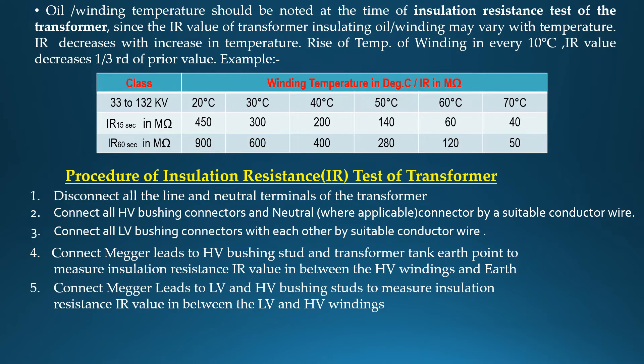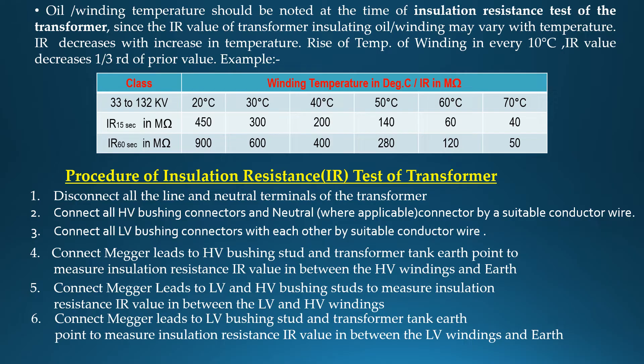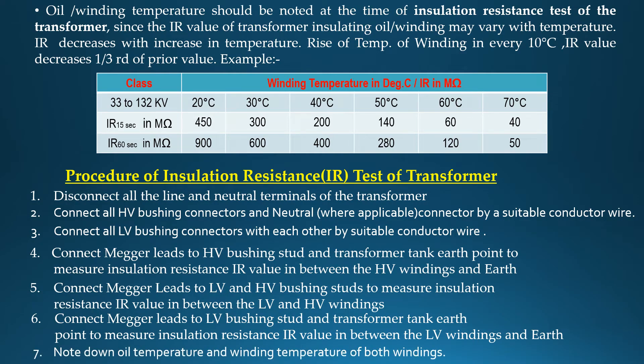Connect megger leads to LV and HV bushing studs to measure insulation resistance IR between the LV winding and HV winding. Connect megger leads to LV bushing stud and transformer tank earth point to measure insulation resistance IR value between the LV winding and earth. Note down the oil temperature and winding temperature of both windings.